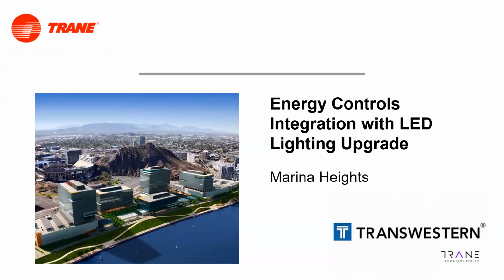This project integrated dimming controls, and it's an interesting case study in how it came together. We went floor by floor each night to retrofit the project. Each morning, when a floor came in and turned the lights on, they came on at only 80% of capacity. Now that the project has run all summer, almost every floor is running at about 60% of capacity.